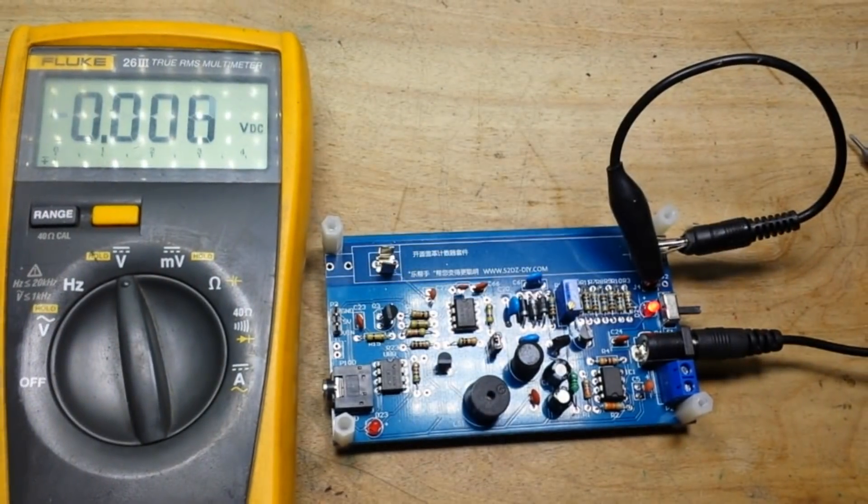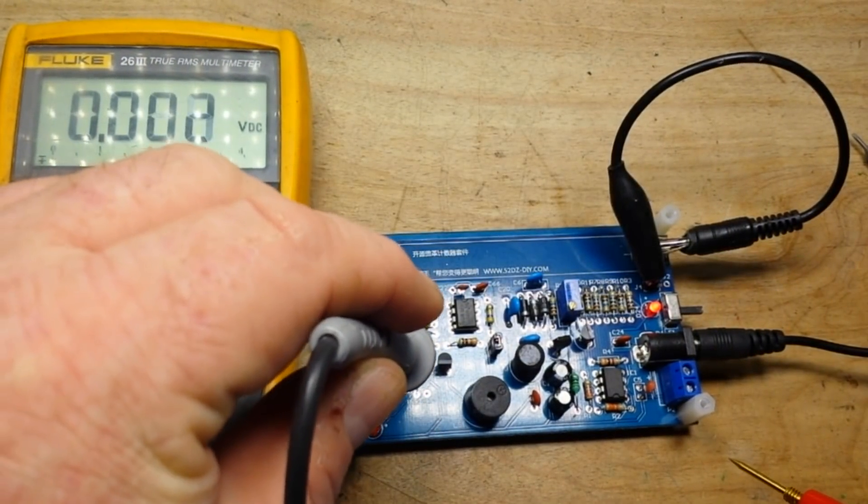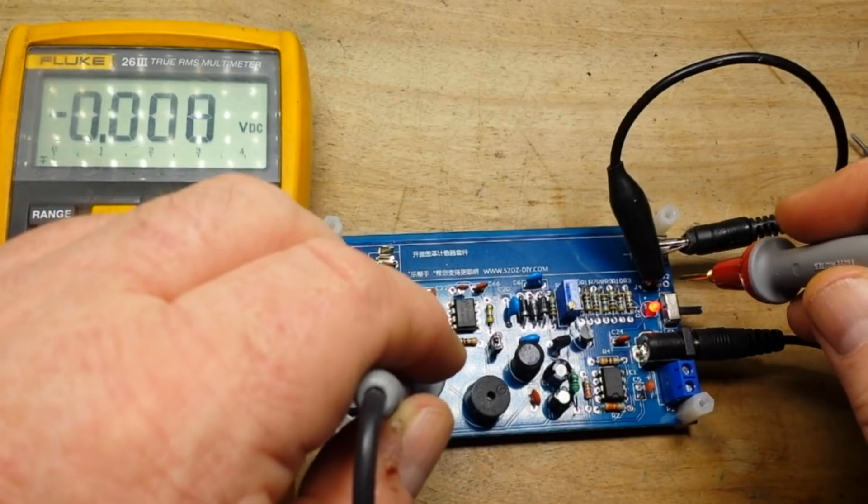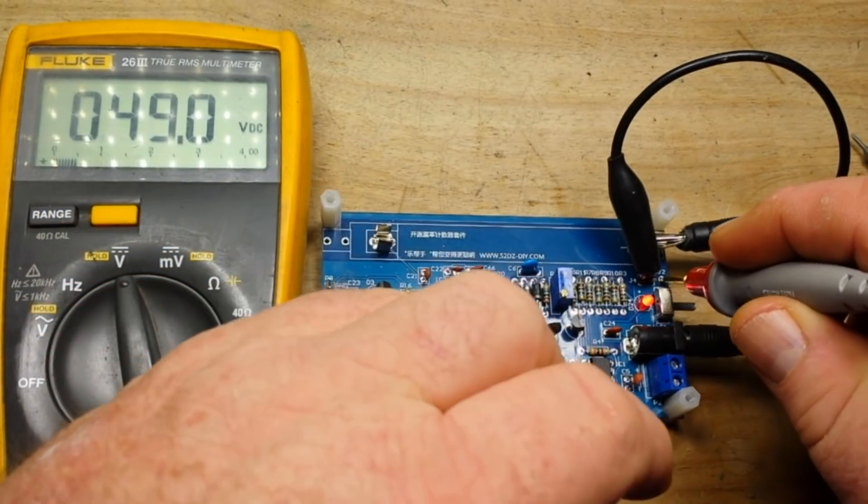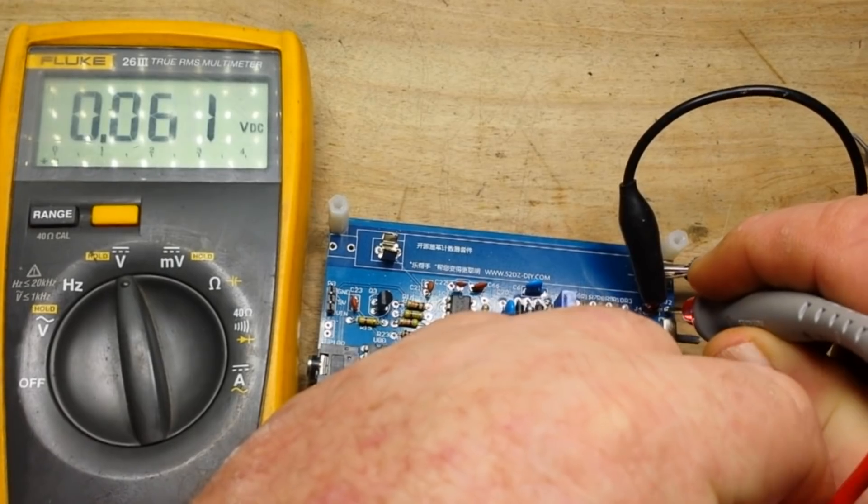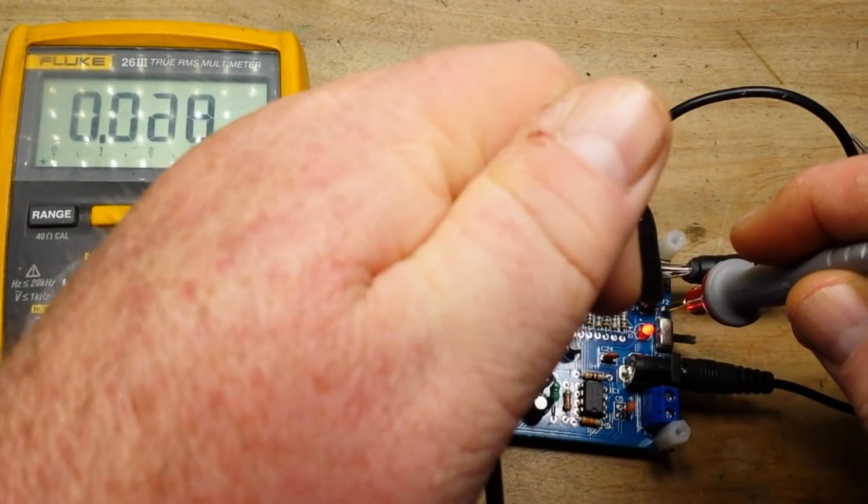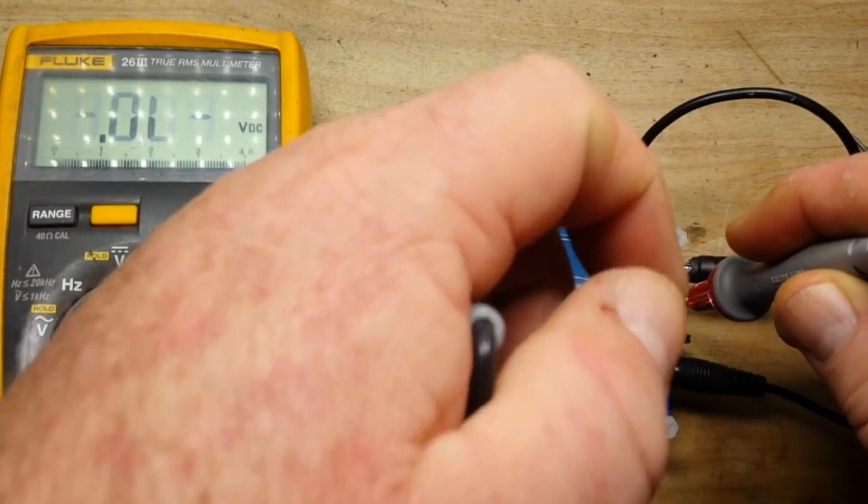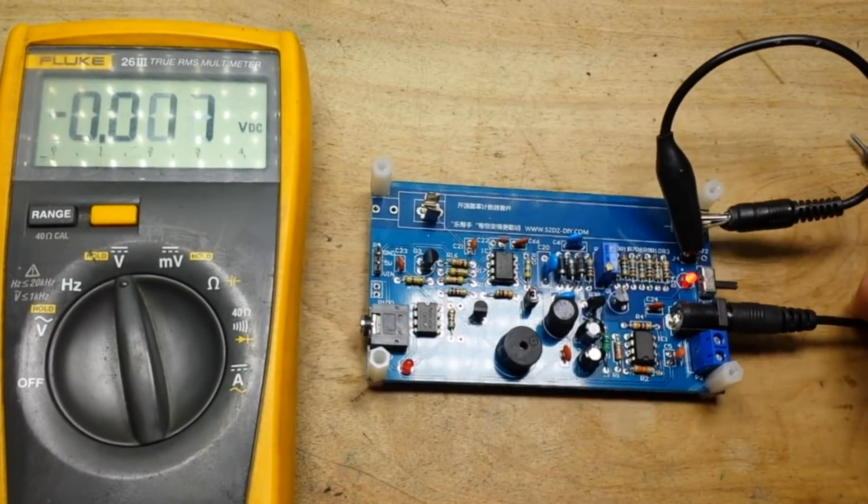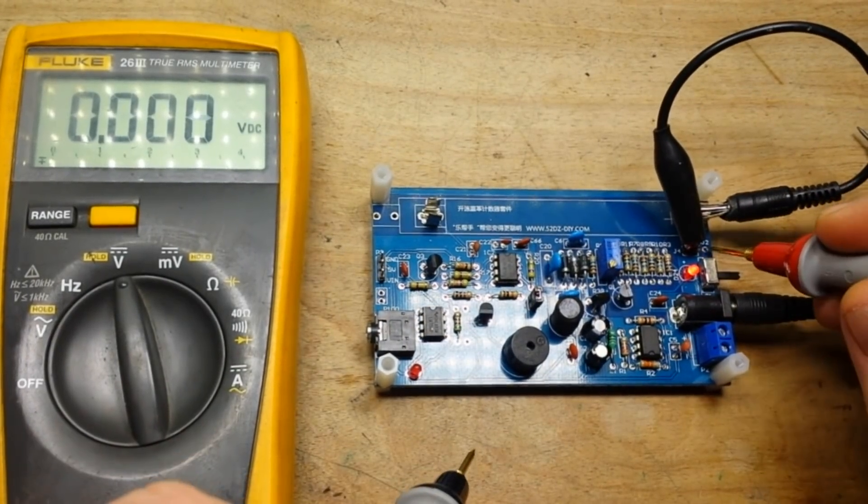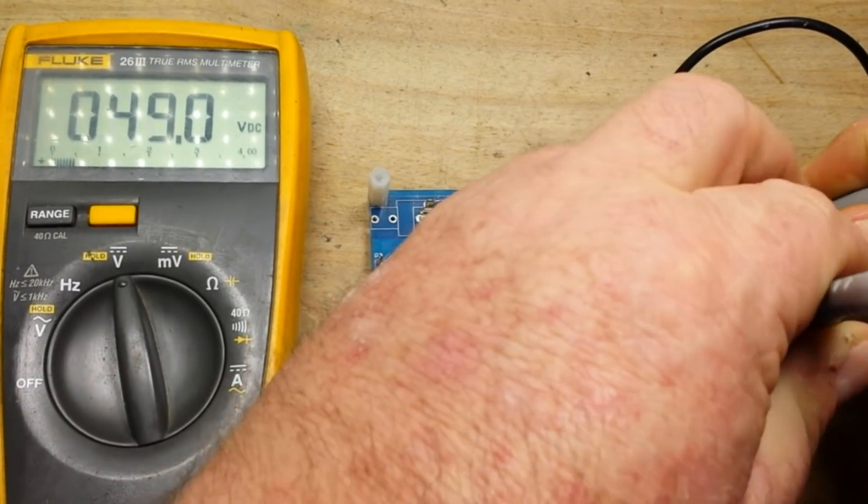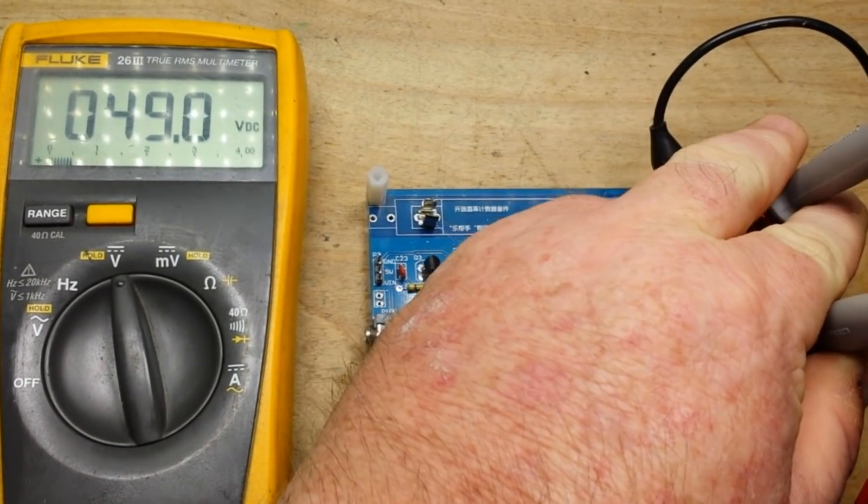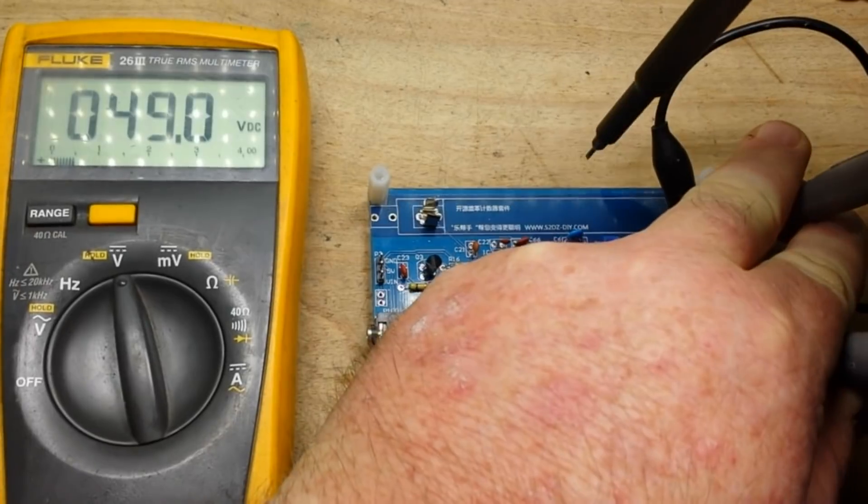It says we are supposed to tune this for 57 volts. Okay, so maybe our voltage is low. Why am I not getting voltage now? Okay, 49 volts, I have to tune that for 57.